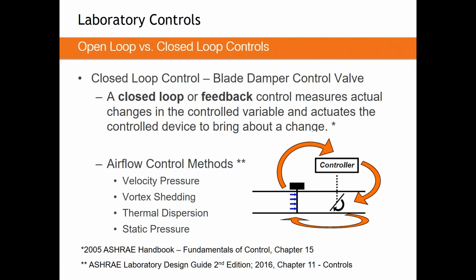There are, however, quite a few different ways to do that. You can measure velocity pressure, which is what your typical VAV box will do. You can do it with a pitot tube, you can do it with an orifice ring, flow cross, lots of things like that. You can use vortex shedding. There are some high accuracy terminals that use vortex shedding, which is a fairly interesting phenomenon where basically you count pulses in the airstream that are caused by obstructions. So you see this really in any moving fluid. You can use thermal dispersion, which is basically the measuring of a drifting heat energy. So if you heat the airstream up and measure how far away that heat drifts, that's called thermal dispersion. It's an extremely accurate way of measuring airflow, actually.